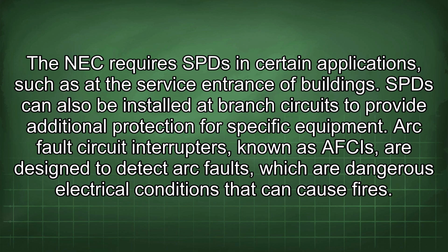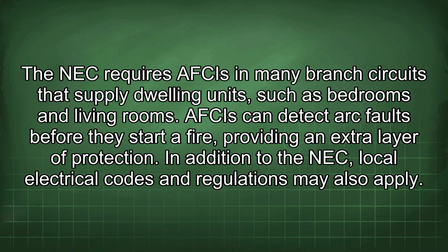Arc fault circuit interrupters, known as AFCIs, are designed to detect arc faults, which are dangerous electrical conditions that can cause fires. The NEC requires AFCIs in many branch circuits that supply dwelling units, such as bedrooms and living rooms. AFCIs can detect arc faults before they start a fire, providing an extra layer of protection.